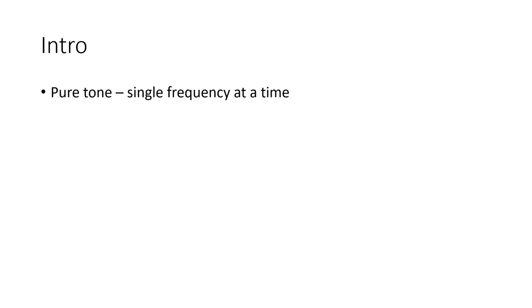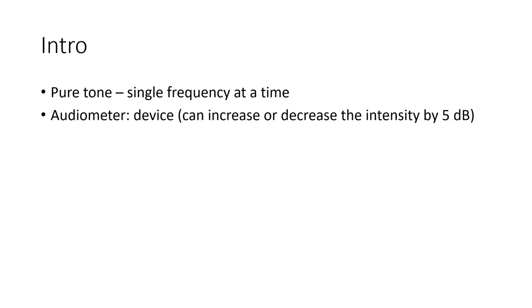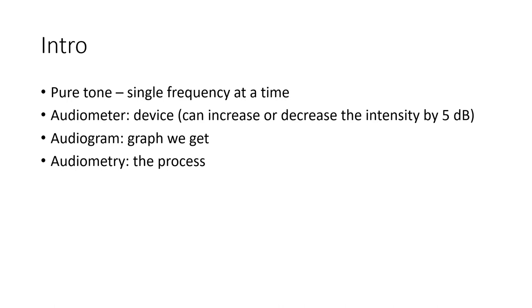Let's get started with the introduction. Why is it called pure tone audiometry? It's called pure tone because it uses the sound of a single frequency at a time. An audiometer is a device that produces sound of a particular frequency, and it can increase or decrease the intensity — that is, the loudness — of that frequency by 5 decibels, to interpret it in an audiogram. That's the graph we get after plotting frequency versus intensity. The frequency is on the x-axis, whereas intensity is on the y-axis. This overall process is called audiometry.